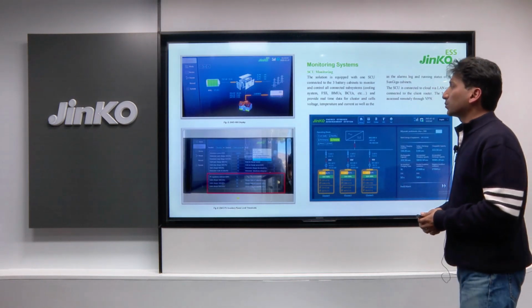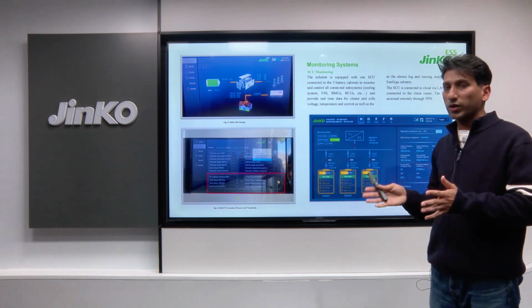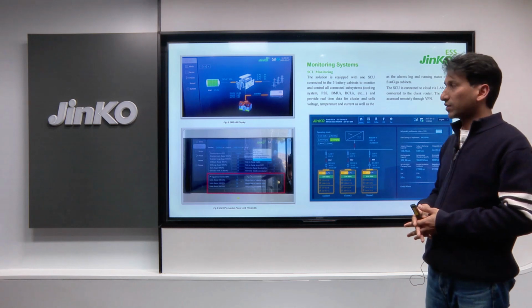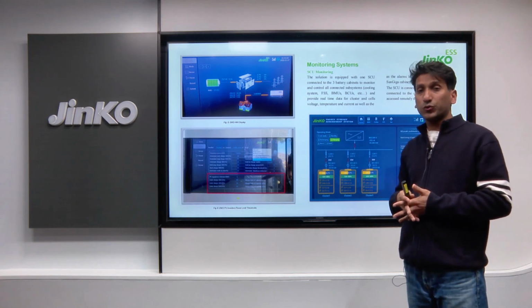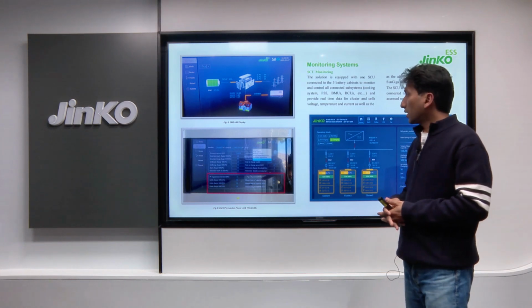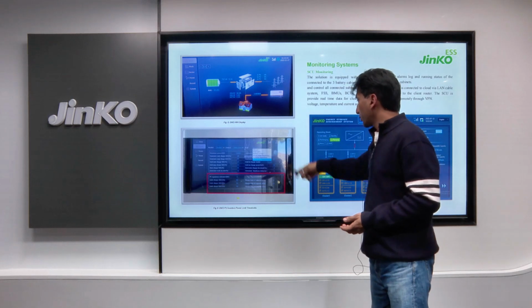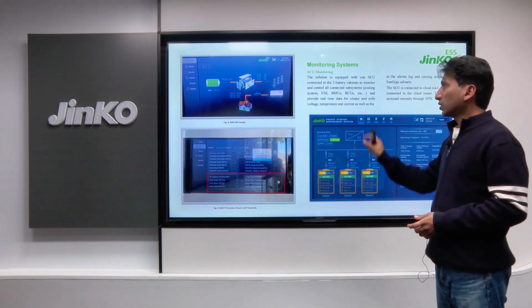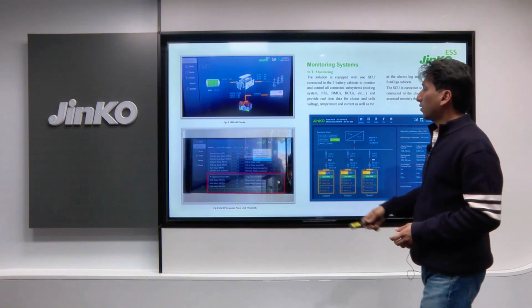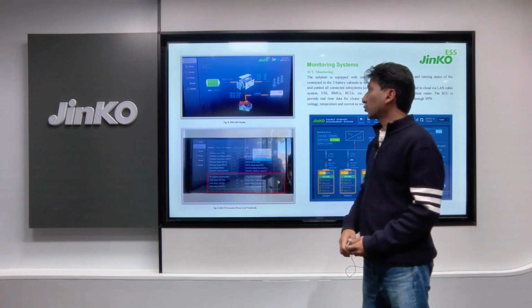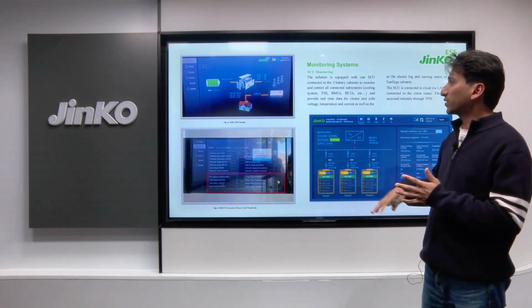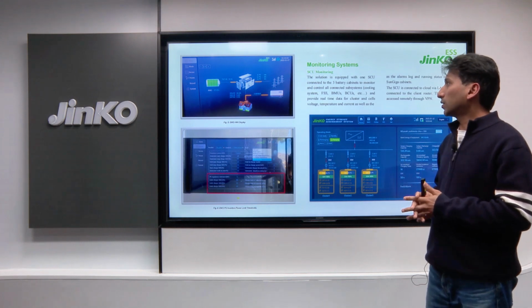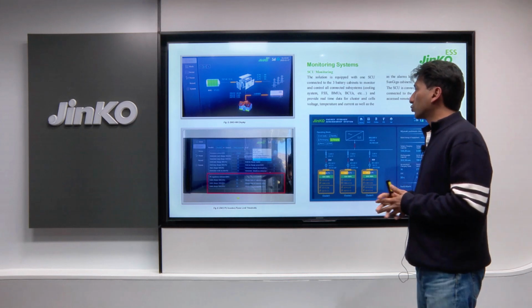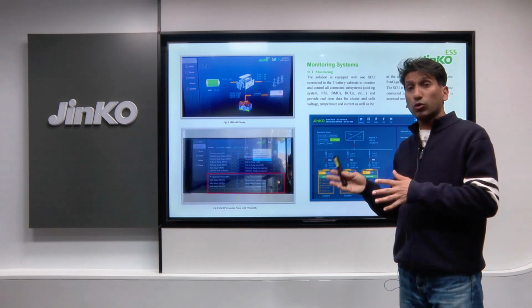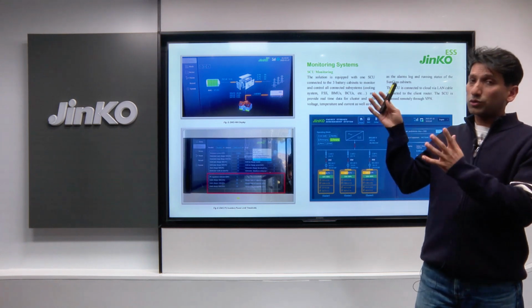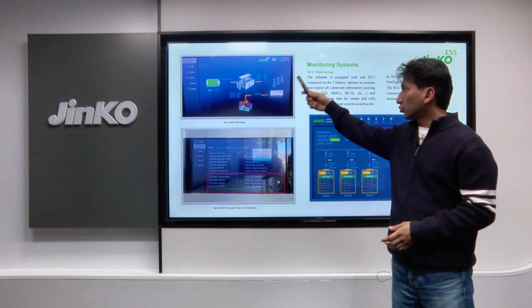Here you can see the monitoring system of our EMS. The EMS is also connected to an HMI, so that we can monitor, control, and set the parameters according to our requirements. Here you can see three different monitoring and control sides of our EMS HMI. On the front side, this interface shows the real-time monitoring of the whole system. It can show you the battery SOC, the voltage of the batteries, and the power flow from the batteries to the load, to the PCS, and from the PV inverters to the other parts of the system.